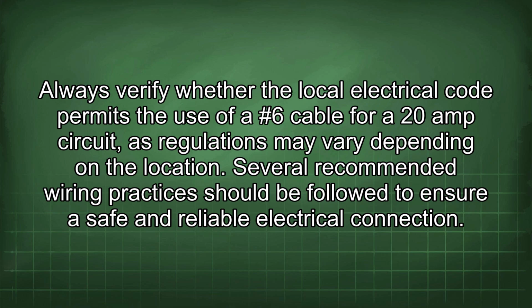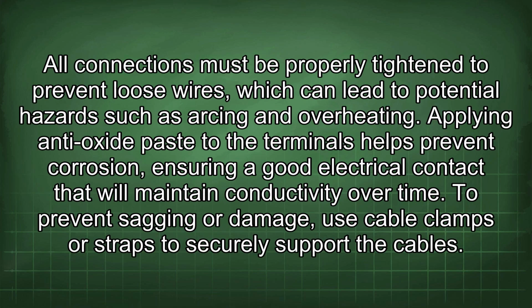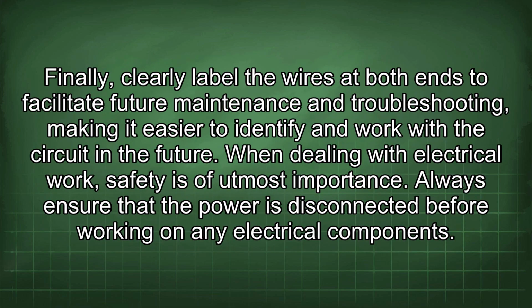Several recommended wiring practices should be followed to ensure a safe and reliable electrical connection. All connections must be properly tightened to prevent loose wires, which can lead to potential hazards such as arcing and overheating. Applying anti-oxide paste to the terminals helps prevent corrosion, ensuring a good electrical contact that will maintain conductivity over time. To prevent sagging or damage, use cable clamps or straps to securely support the cables. Finally, clearly label the wires at both ends to facilitate future maintenance and troubleshooting, making it easier to identify and work with the circuit in the future.